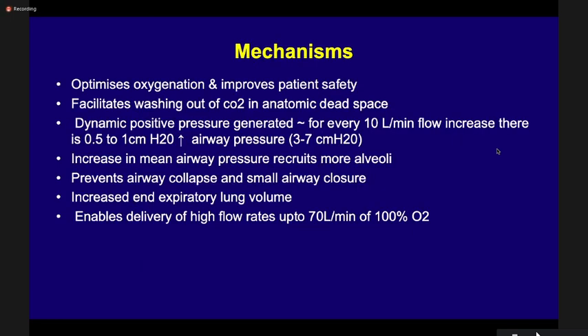It optimizes oxygenation and improves patient safety. It facilitates washing out of carbon dioxide in the anatomical dead space. This dynamic positive pressure is generated such that for every 10 liters per minute flow increase, there is a 0.5 to 1 centimeter water increase in airway pressure. So the airway pressure is maintained around 3 to 7 centimeters of water. There is an increase in mean airway pressure, which recruits more alveoli.